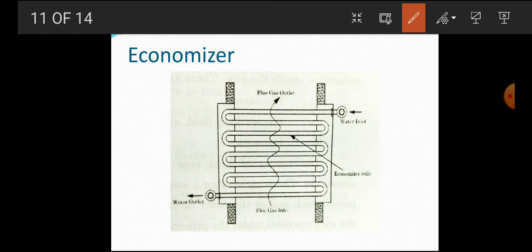The economizer is an accessory to the boiler where it is used to recover waste heat. It takes heat from the flue gases and passes that heat to the inlet water, so that the water gets heated and less fuel is required to generate steam. It is used in order to utilize the boiler feed water using the heat of flue gases. Due to this heat utilization of flue gases, the fuel required to heat the feed water is significantly reduced.